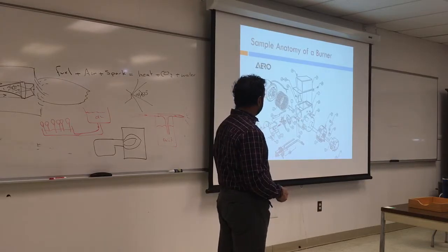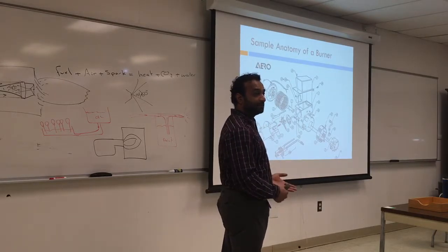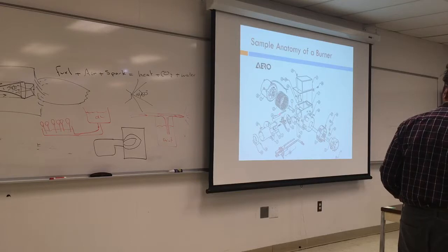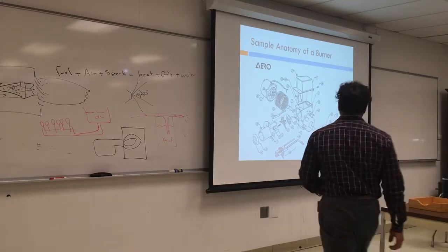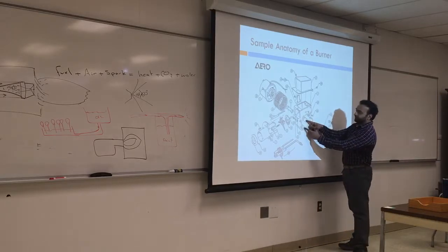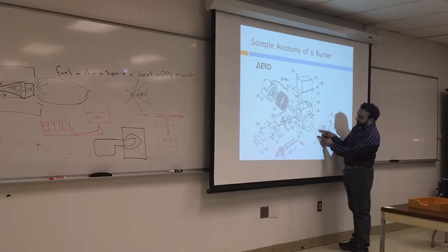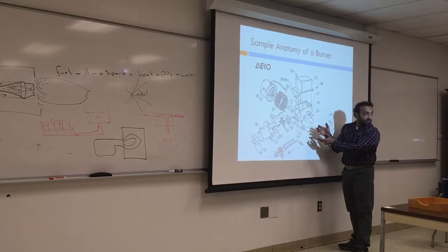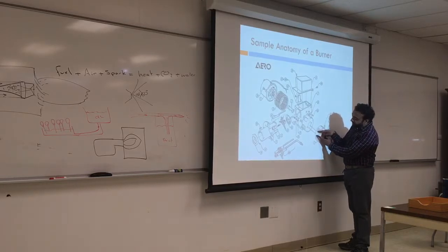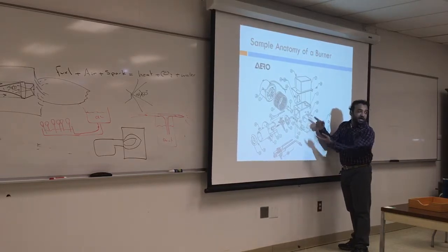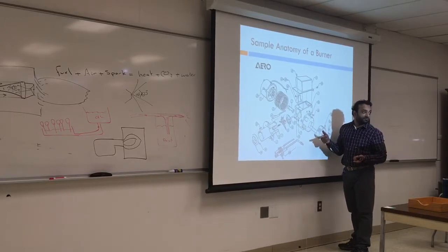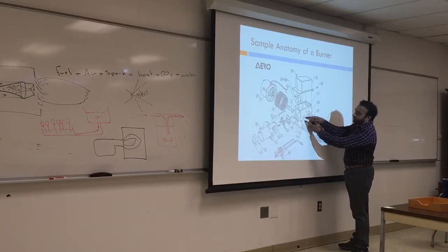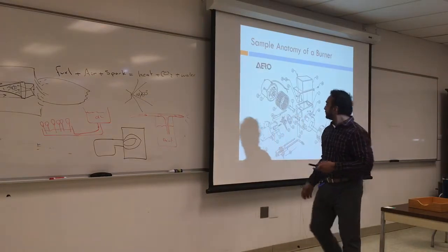Any question about the schematic? You already took apart the whole burner and put it back again, so hopefully you remember. I just wonder, the number 4. Number 4, right here, this is the air band. So you see these holes in here? They're always open. These air bands have holes in them and have solid parts. By twisting it back and forth, you can control the opening, how much air you get in there. Oh, okay. So if I align these solid parts with the holes here, I have almost no air coming, a very, very little amount of air. If I have the slots here on the opening, you'll get more air inside the chamber.